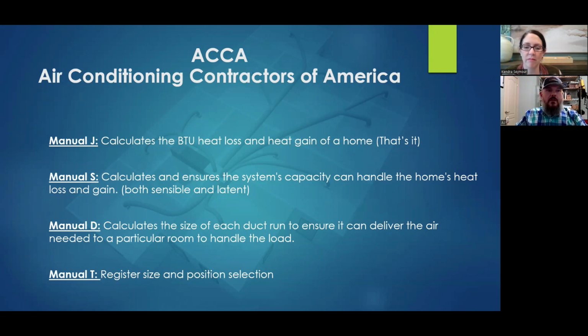Manual D calculates the size of each duct run to ensure it can deliver the air capacity needed to a particular room to handle the load. Manual T calculates the register size and position in the room to ensure you get good air mixing, throw, and spread.